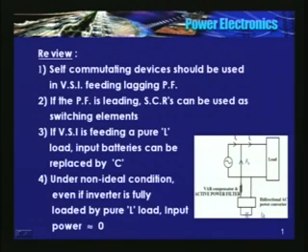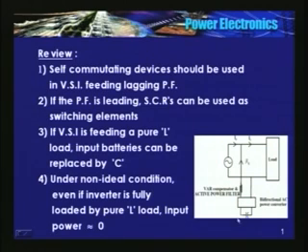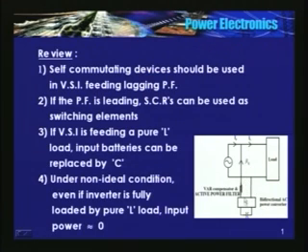This is the voltage source inverter where the capacitor is the input and the output is available at this point. The real power transferred by the source to this inverter is very small — just enough to overcome the inverter losses and I²R of the inductor. This unit can supply both leading as well as lagging current by controlling the magnitude of the output voltage of the voltage source inverter. This is a very important piece of equipment.